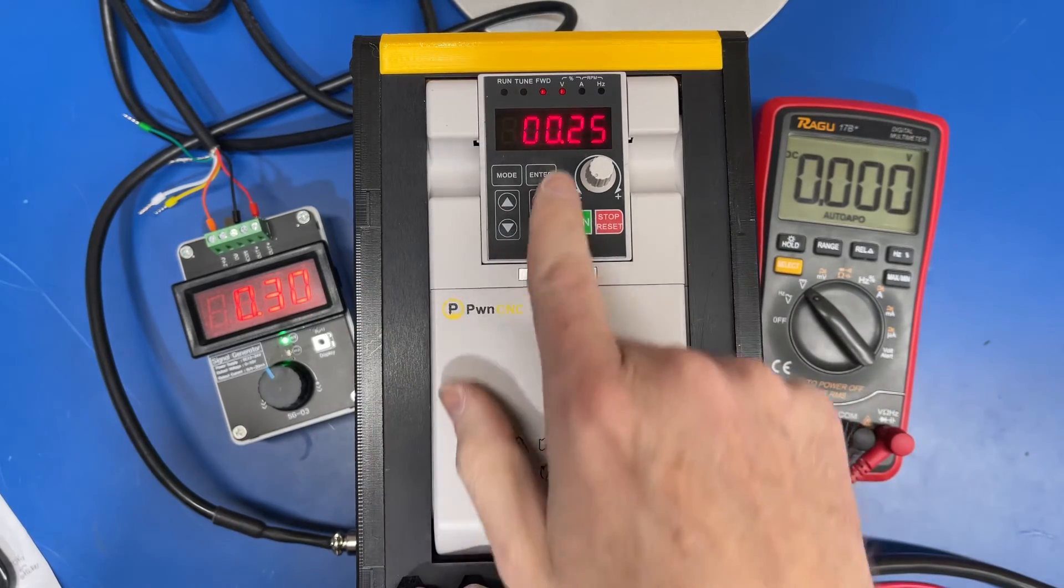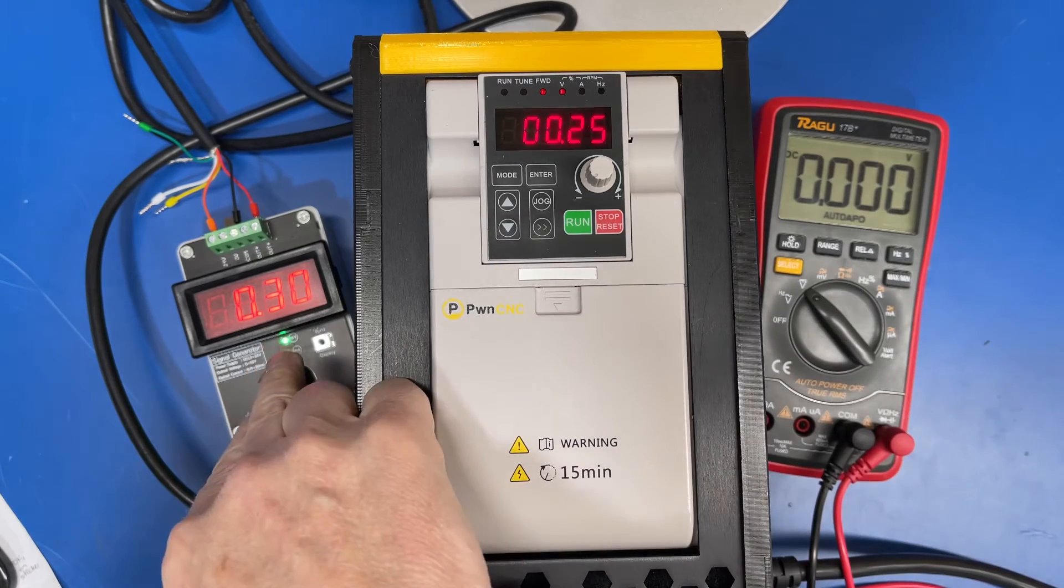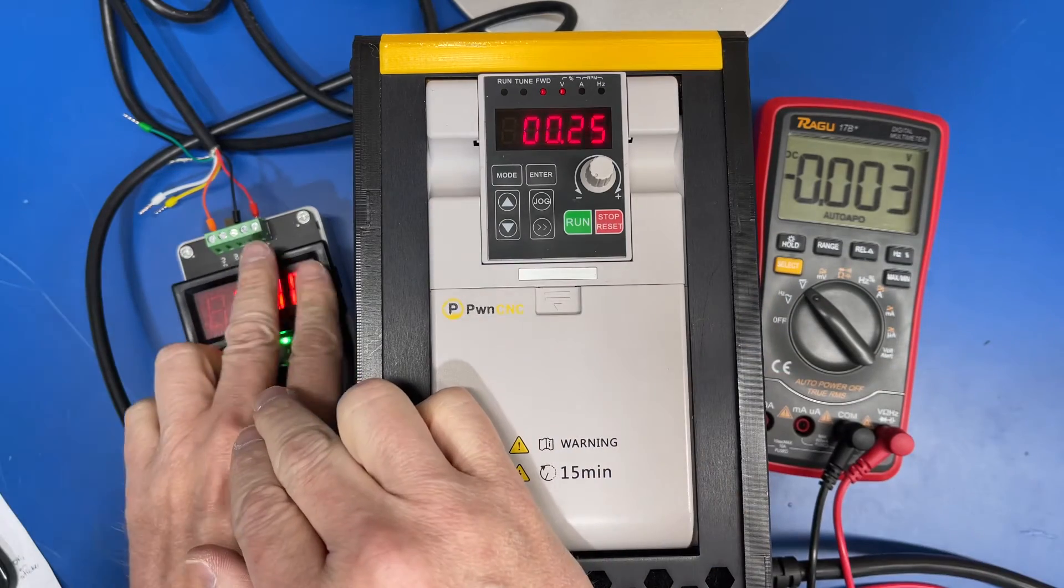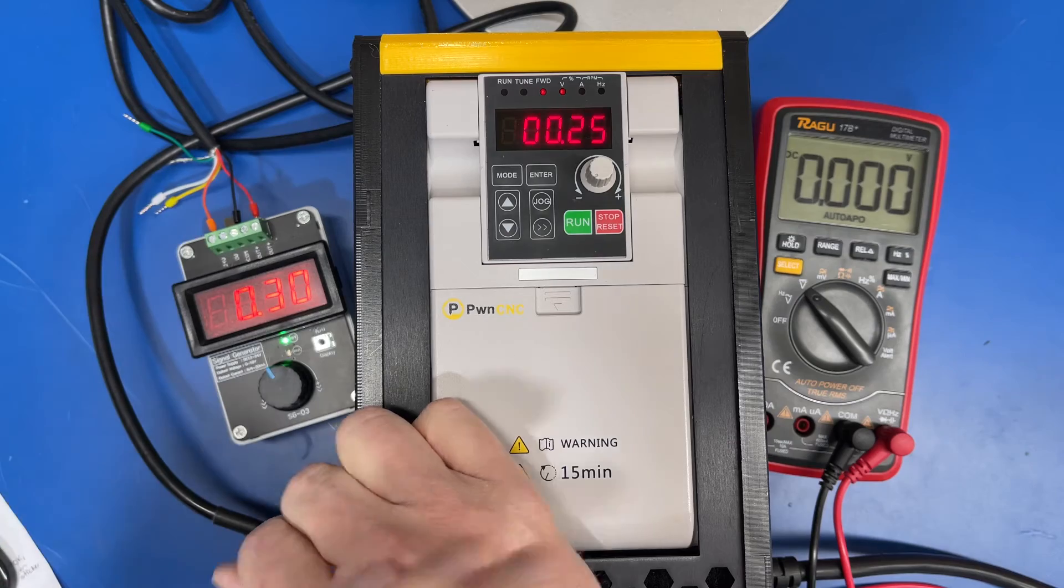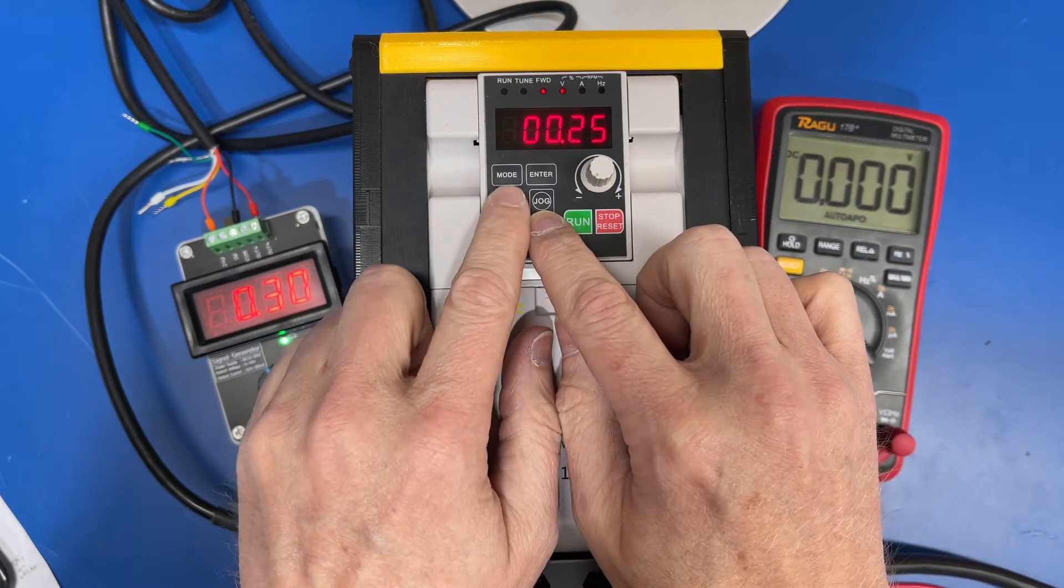Hit enter. I've got it set at 0.25, so anything below 0.25 volts is ignored. But clearly I've set it at 0.3. So let's say if we measured it, your controller at zero RPMs is still outputting a 0.3 volt signal. We can adjust this setting here so it is at the minimum voltage that it should be seen. So if we back out of that.